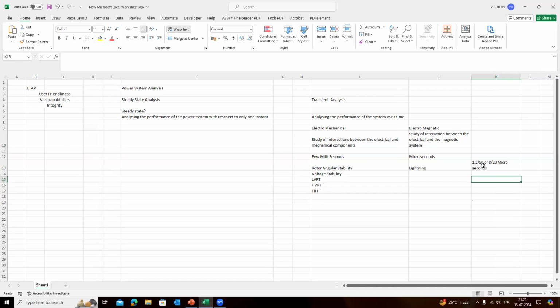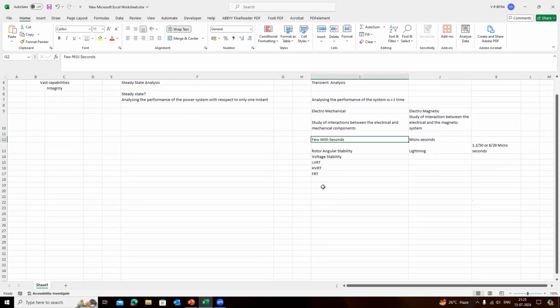So what is the time step which you need to use? Very, very small. Whereas in the electromechanical transient, the event happens in few seconds. So if you are putting the time step as a few milliseconds, it's good to go for electromechanical transient studies - like when I'm studying sudden load disconnection, what is the rise in frequency? For that I need not run the simulation with microsecond or nanosecond time step; a few milliseconds is good enough.